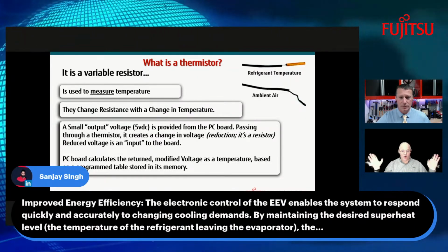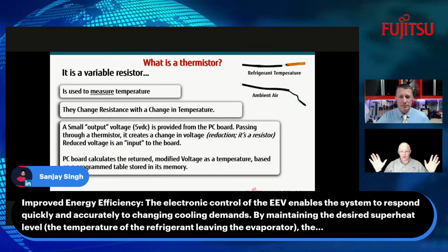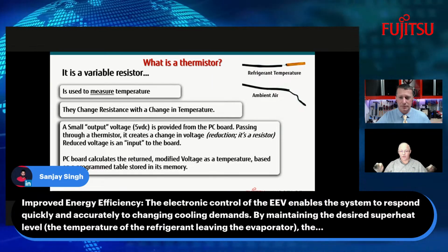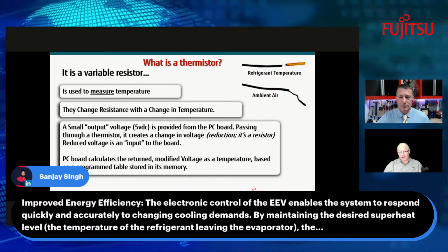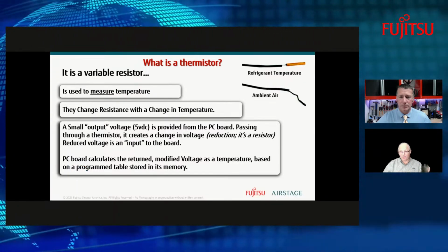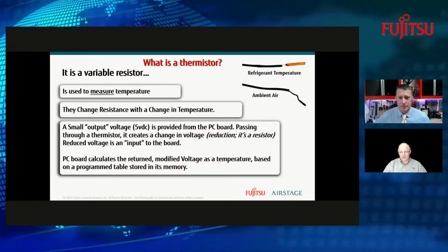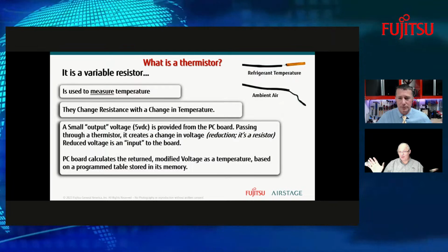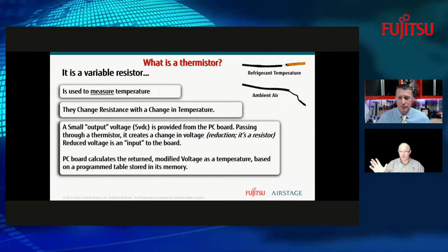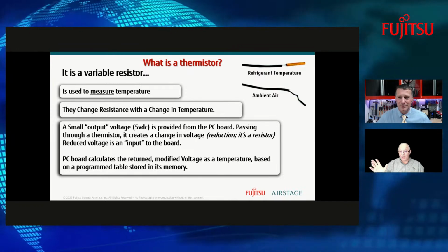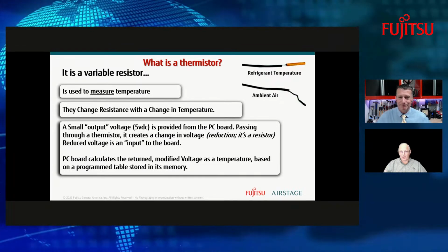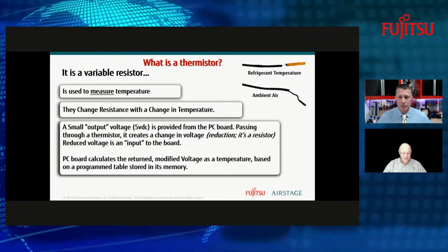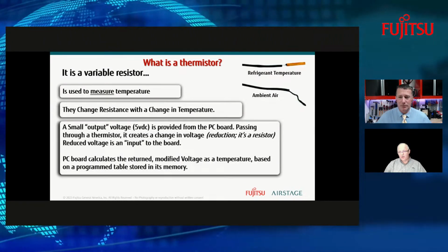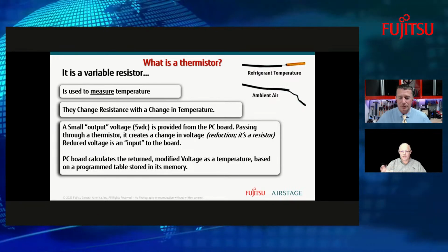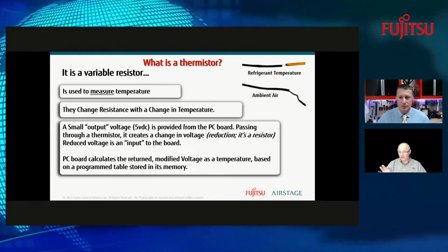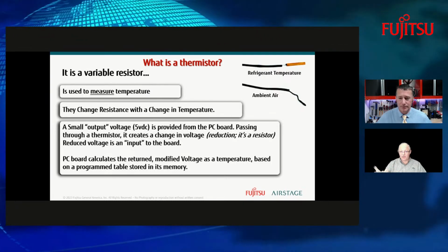It's not like the thermistor says, "Oh, I'm 75 degrees" or whatever. It's looking for a drop in the voltage going through that, and whenever that voltage comes back to the input board, that information is then going to be sent to the outdoor unit, and it's going to say, "Here's what's happening inside." And the outdoor unit says, "Oh, I see your voltage is changing. It looks like it's getting warm in there," and then it starts to tell the system it's time to modulate. So it's a very interesting correlation between the indoor thermistors and the outdoor thermistors, all sending information to the outdoor board and telling it, "Here's where we're at," and then it makes the decision on what it's going to do.